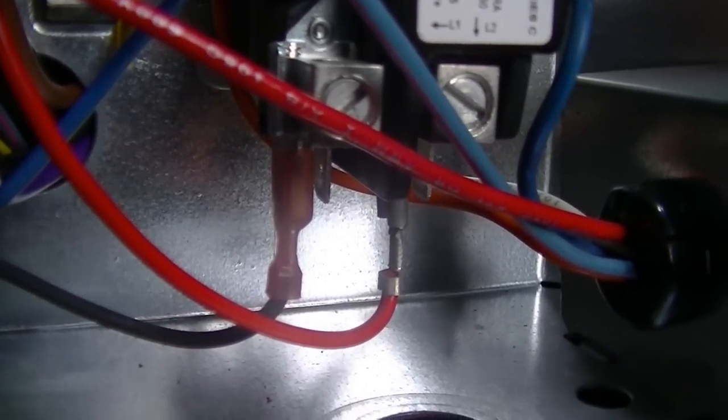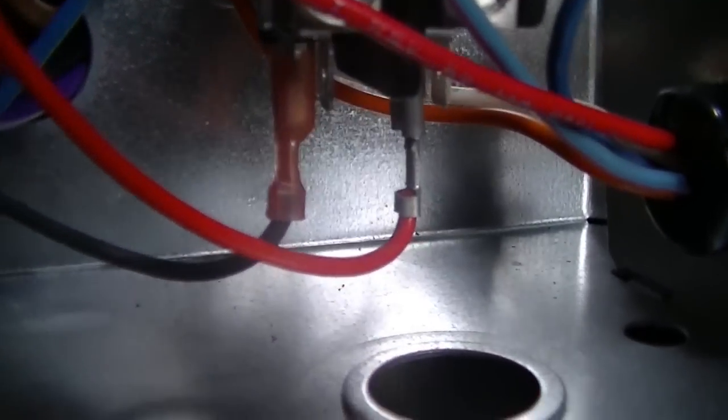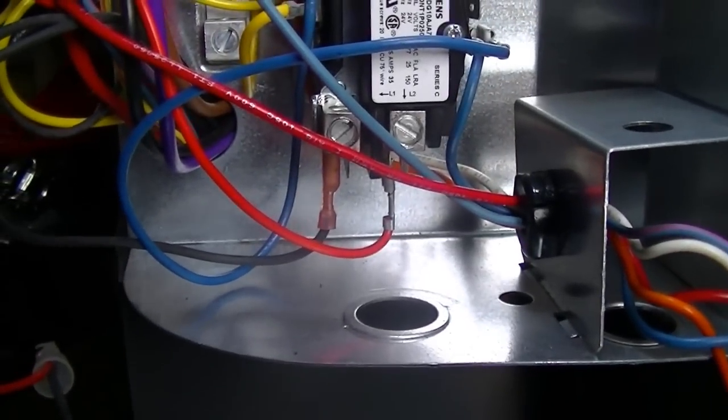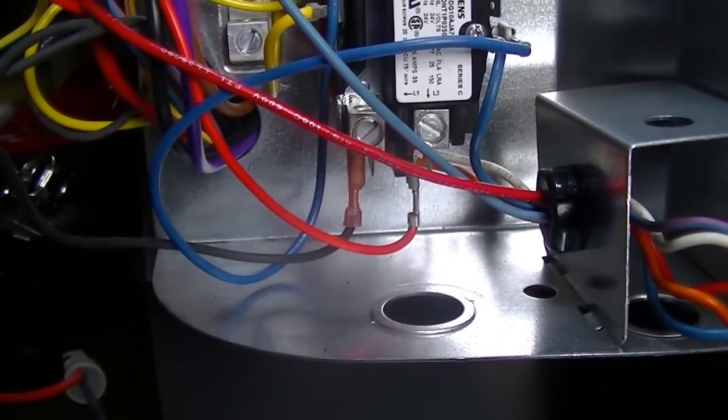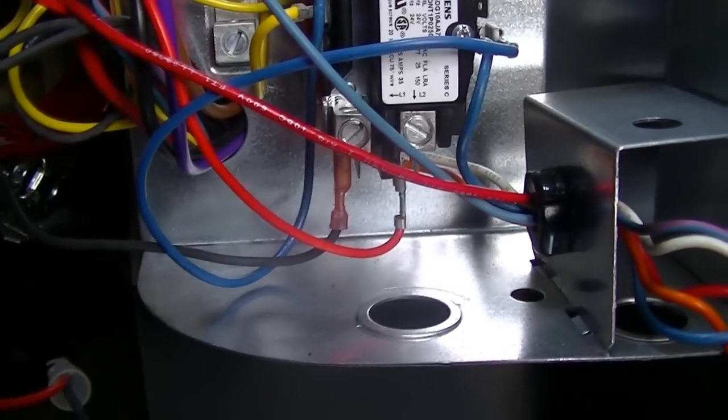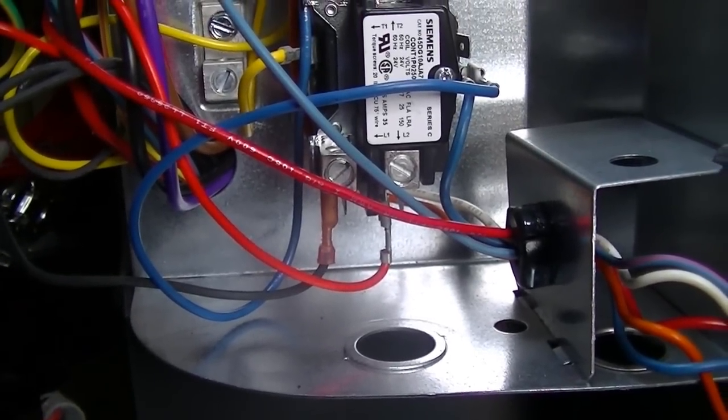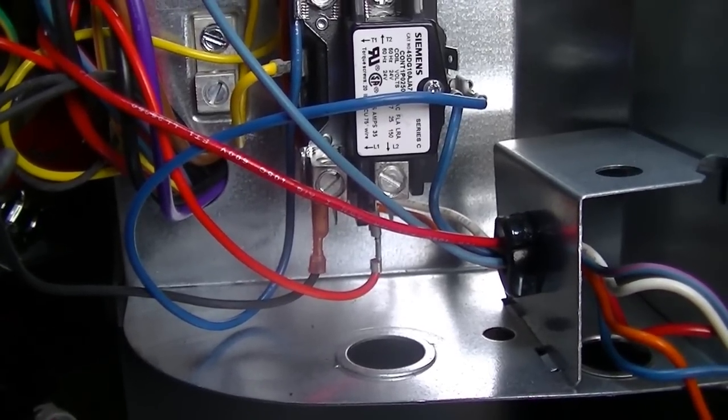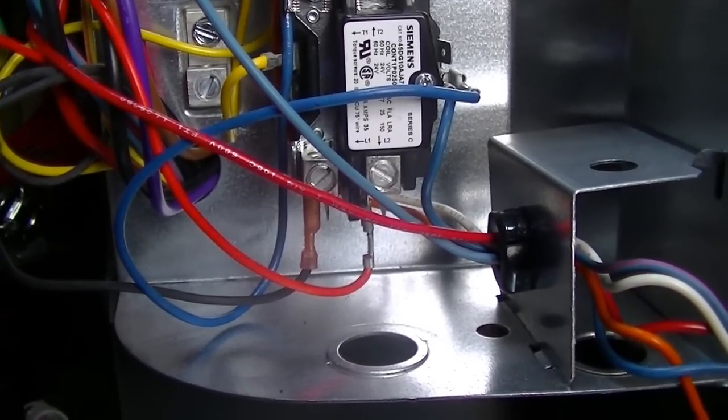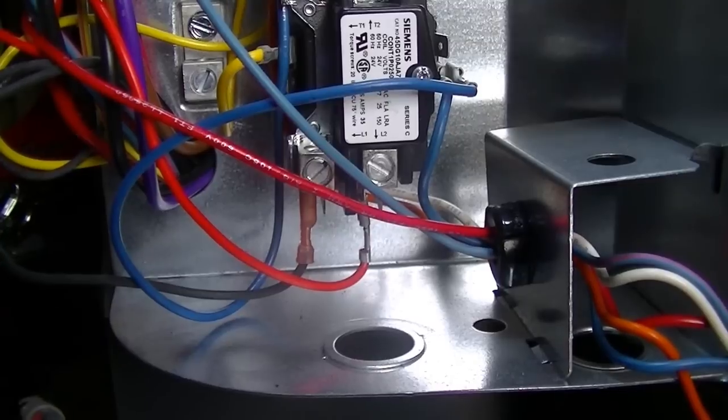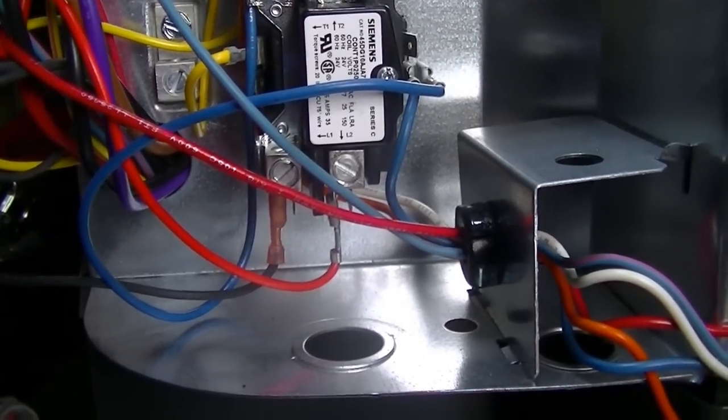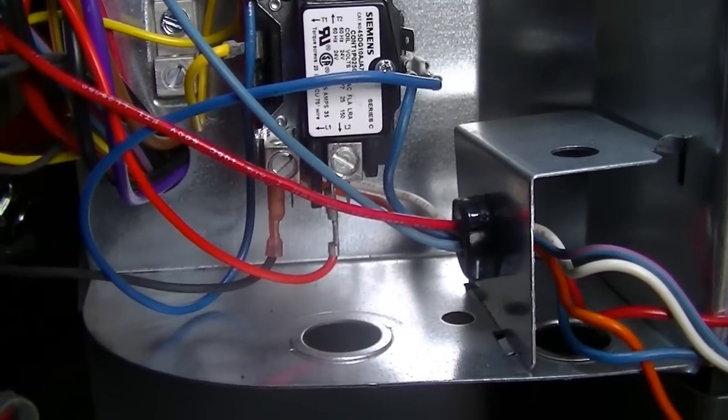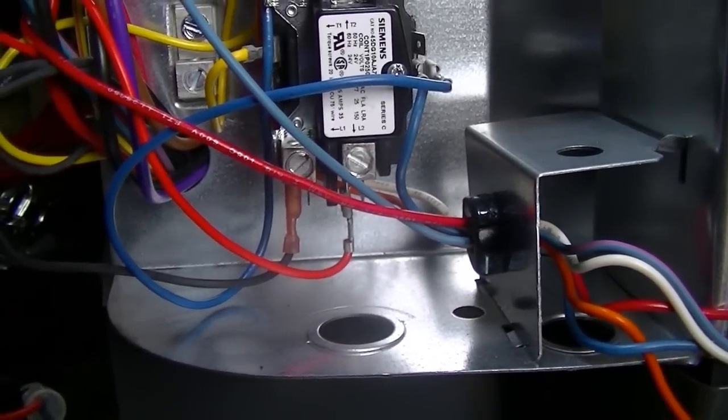As you can see on the bottom of the contactor, there are two wires, a black and red. One of those wires goes to the crankcase heater. Another wire goes to the crankcase heater sensor, and it's a temperature sensor that looks just like a defrost thermostat. And what happens is when the compressor comes on, it heats up the sensor, opens the circuit, and the crankcase heater goes off. Pretty simple. Like I said, it looks just like a defrost thermostat. It's clipped to the discharge line of the compressor. This one's located a few inches after the muffler.